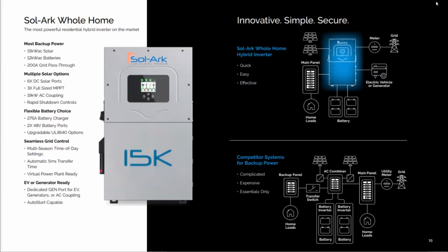But what I think a lot of installers are missing is the functionality of the gen port on the Sol-Ark. If you're not using the gen port for a generator, and there's a lot of areas in California that are not generator friendly, if you're doing a grid tied system and you're not using the gen port for a generator, it is possible to tie in a sub panel, and that will give you a state of charge based load sheddable sub panel.